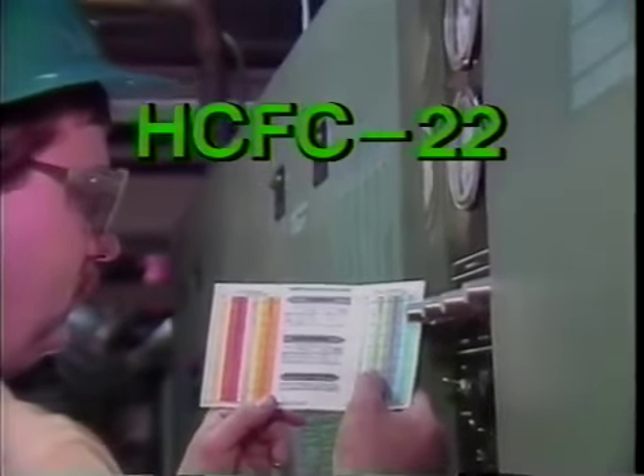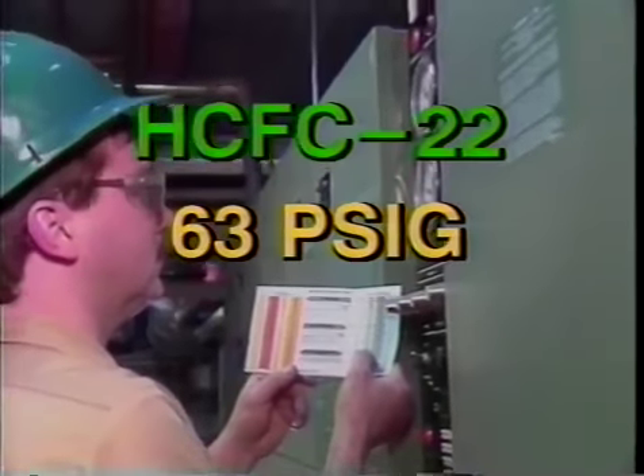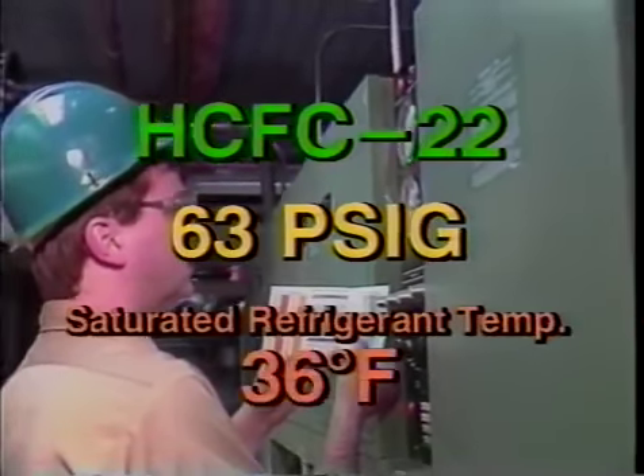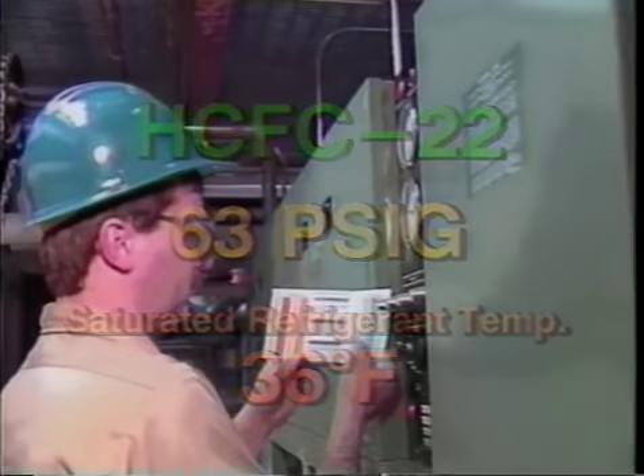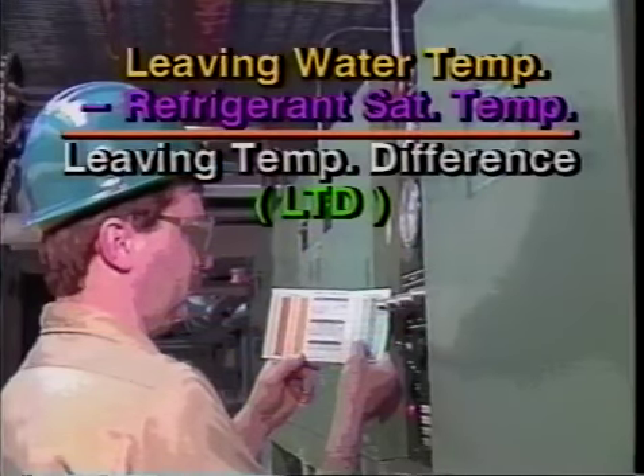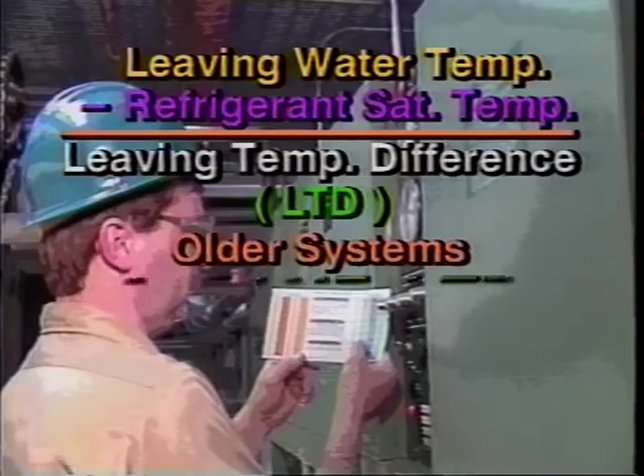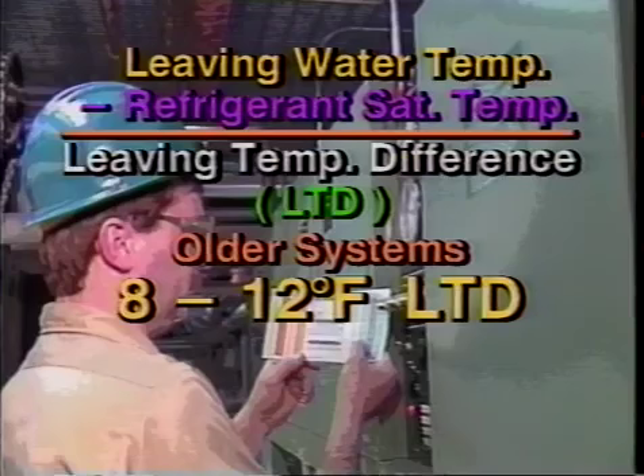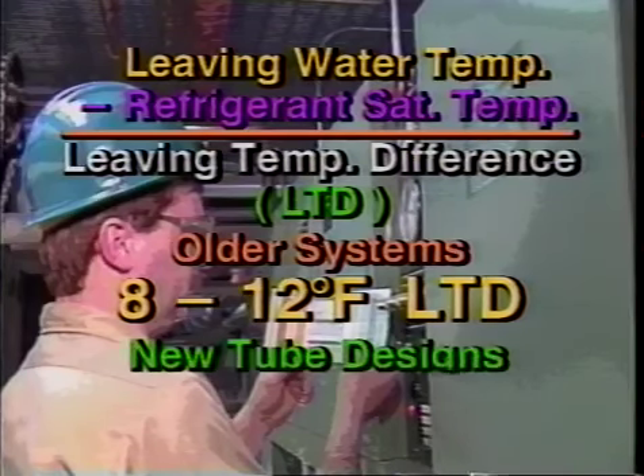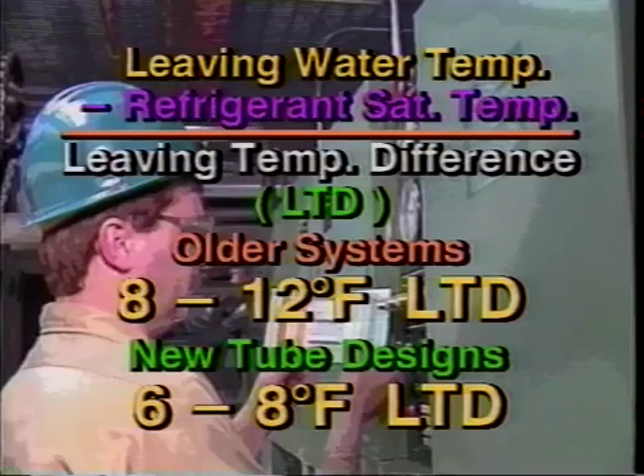We're using HCFC 22 refrigerant, and the suction pressure is 63 psig, which means our saturated temperature in the cooler is 36 degrees Fahrenheit. The difference between the refrigerant saturated temperature and the leaving water temperature is often referred to as leaving temperature difference, or LTD. It's an important relationship, and in a properly operating HCFC 22 system, this difference will normally be from 8 to 12 degrees Fahrenheit on older chiller systems. More recent cooler tube designs provide a much better heat transfer with LTDs being around 6 to 8 degrees.